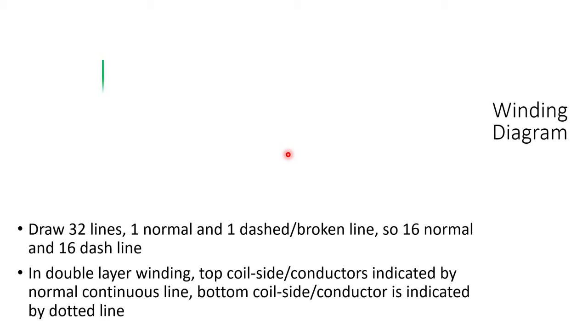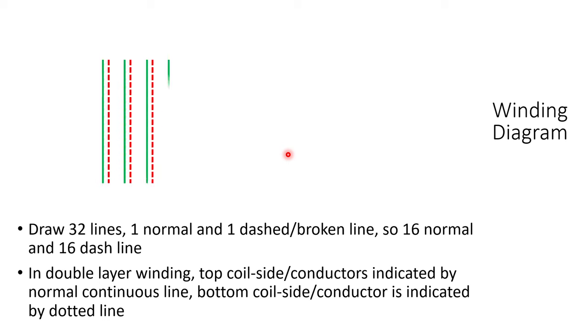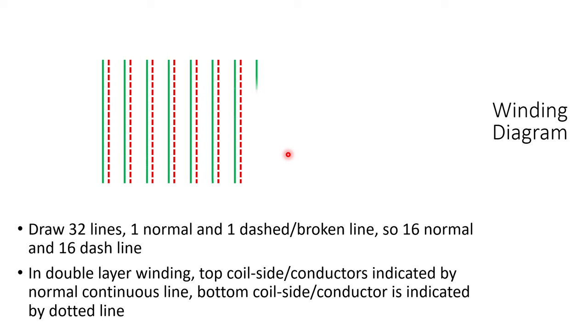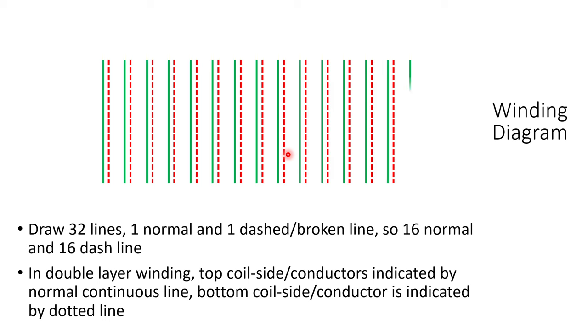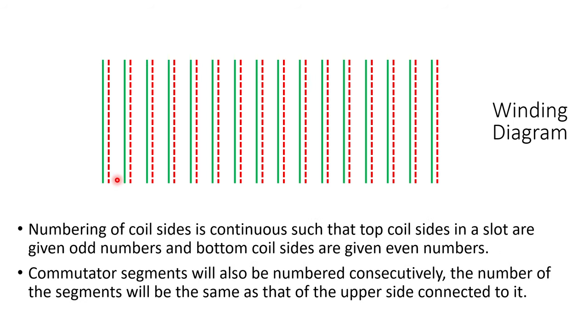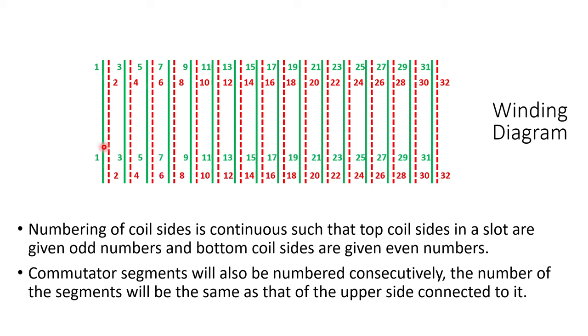Referring this winding table, we will now draw 32 lines — 16 normal and 16 dashed or broken lines. In double layer winding, the top coil side is indicated by a continuous line and the bottom coil side is indicated by a dotted line. Numbering of coil sides is continuous such that top coil sides in a slot are given odd numbers and bottom coil sides are given even numbers. Commutator segments will also be numbered consecutively, and the number of a segment will be the same as that of the upper coil side connected to it.